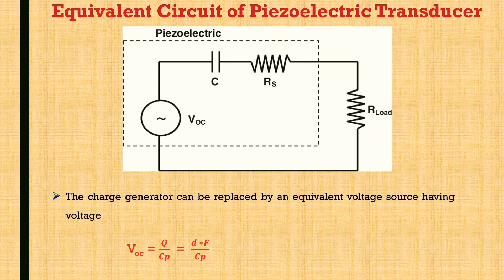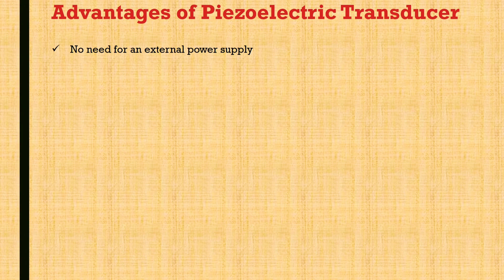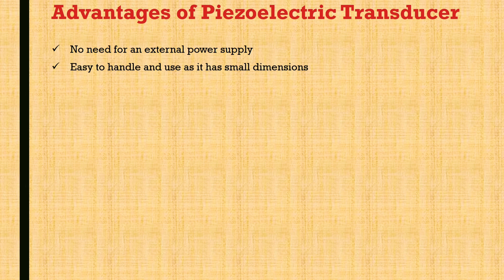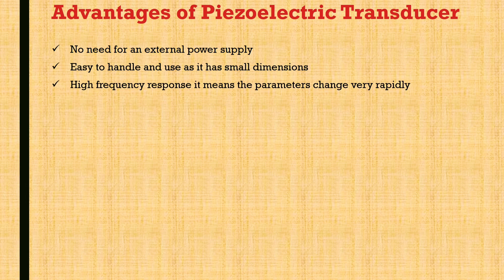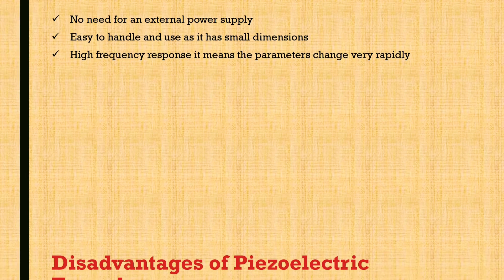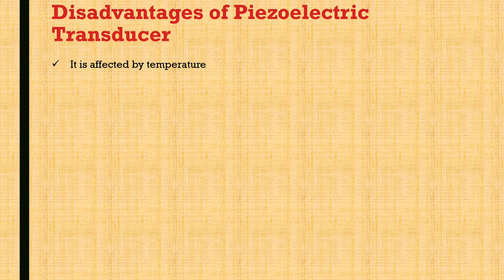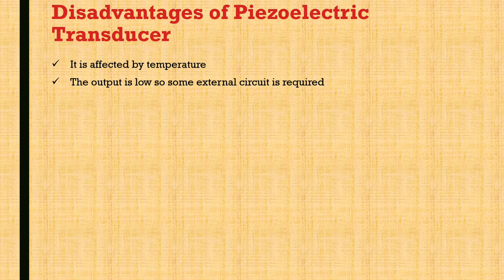The advantages of piezoelectric transducers include: no need for an external power supply, easy to handle and use, small dimensions, and high frequency response — meaning parameters can change very rapidly. The disadvantages include: it is affected by temperature, the output is low so external circuitry is required, and it is not suitable for measurement under static conditions.